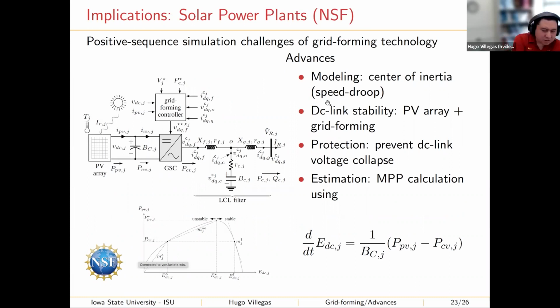So some of the advances we made here is modeling the center of inertia. For example, imagine that you have a power system that only has grid forming inverters, and the problem comes how to define the center of inertia of that system. Typically, when we have only machines, we define the center of inertia as some sort of weighted average of the inertia of those machines. But we also tackle here the DC link stability problems.